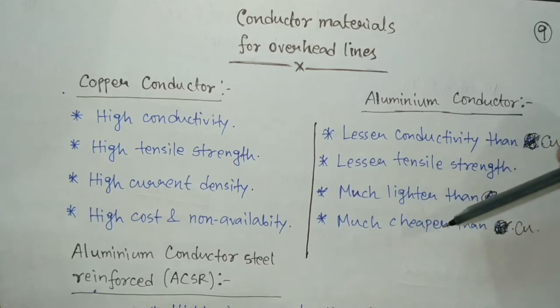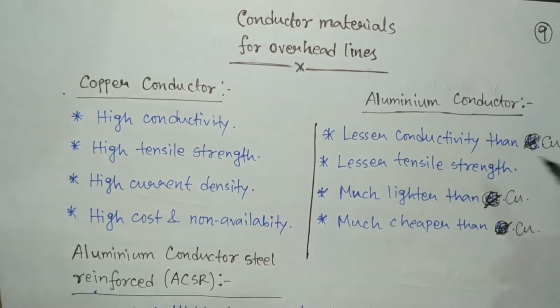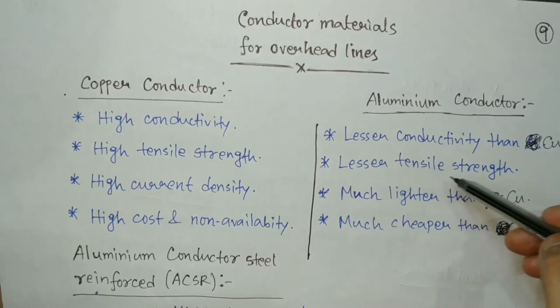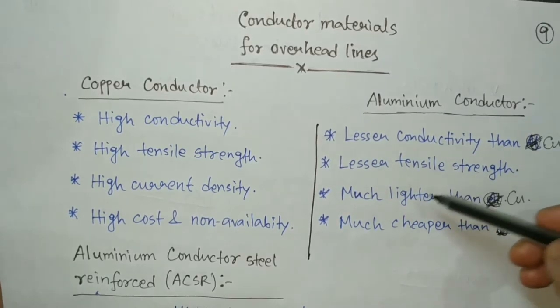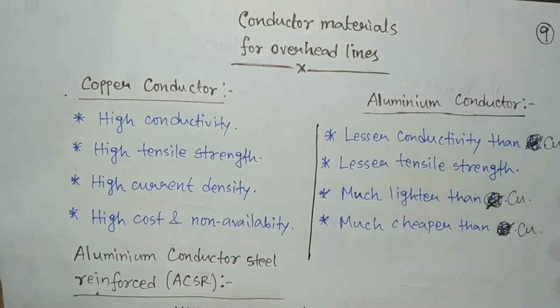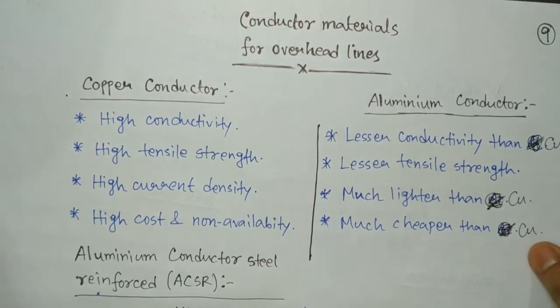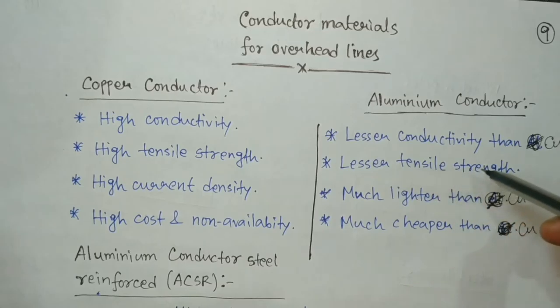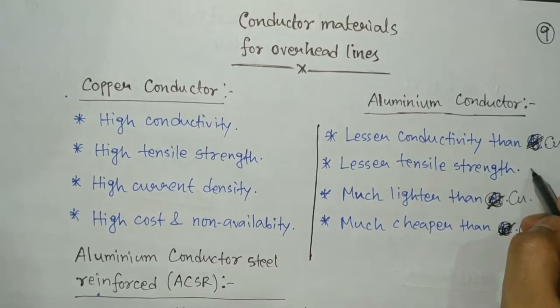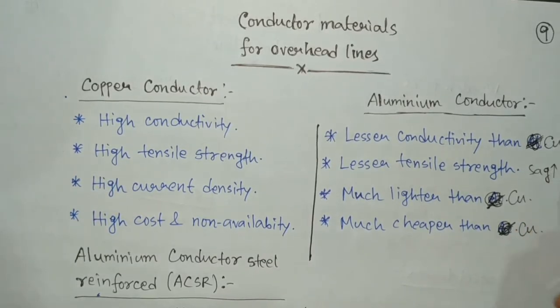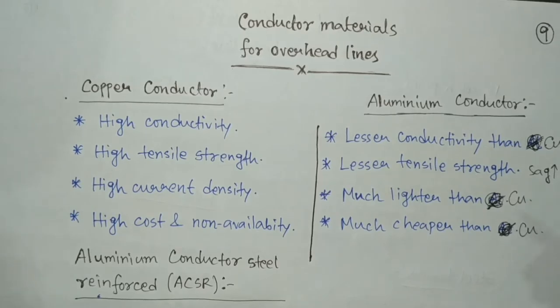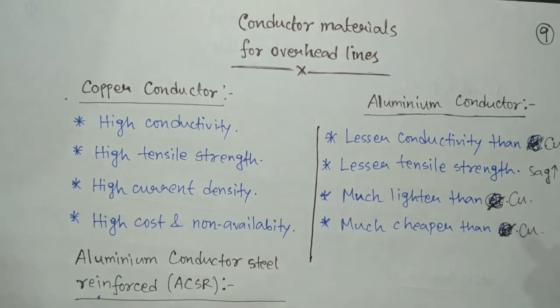Nowadays people prefer aluminium conductors in long transmission due to their cheapness and lightweight. Unfortunately, aluminium conductor has lesser conductivity than copper and also lesser tensile strength. But it is much lighter and much cheaper than copper. However, the lesser tensile strength of aluminium results in high sag, which is a significant problem.